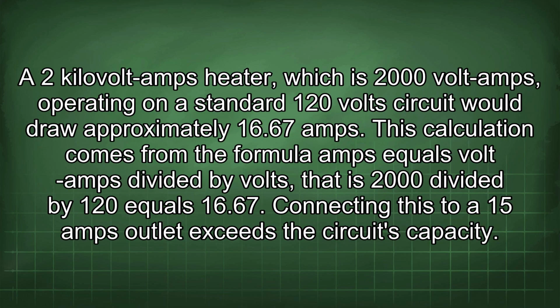A 2 kVA heater, which is 2000 volt-amps, operating on a standard 120 volt circuit would draw approximately 16.67 amps. This calculation comes from the formula amps equals volt-amps divided by volts. That is 2000 divided by 120 equals 16.67. Connecting this to a 15 amp outlet exceeds the circuit's capacity.